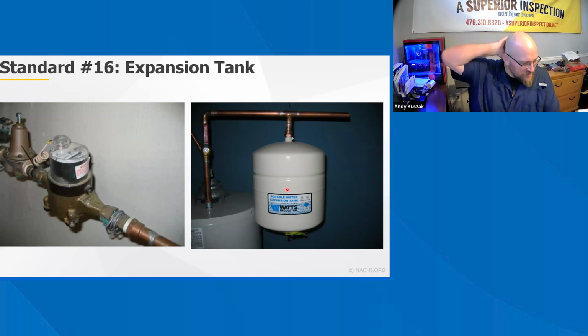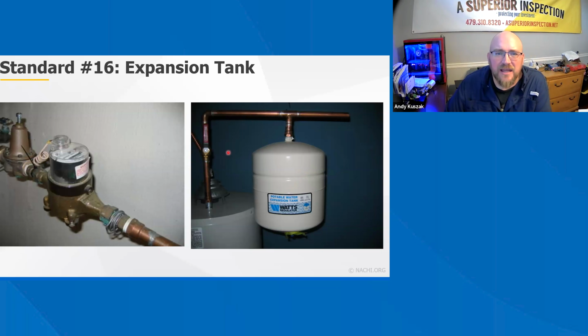All right, so expansion tanks are taking an interesting evolution. It's kind of going backwards in a way. They started out with an inline thermal expansion valve, and then they evolved into this big expansion tank, and now they're going back to an inline expansion valve. So you may or may not see this big tank anymore, but you may see a thermal expansion valve that has a drain coming off of it if the pressure gets too big. It's kind of like a temperature pressure relief valve, but it's for pressure, and it's inline, and it'll have a little drain coming off of it, a lot of times going into the same drain that your temperature pressure relief valve is going into.